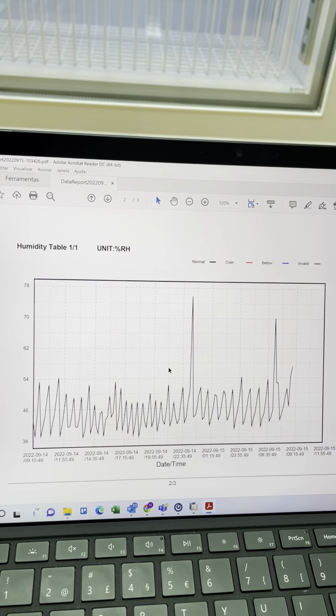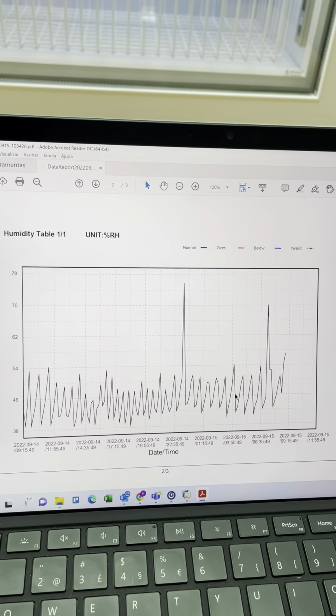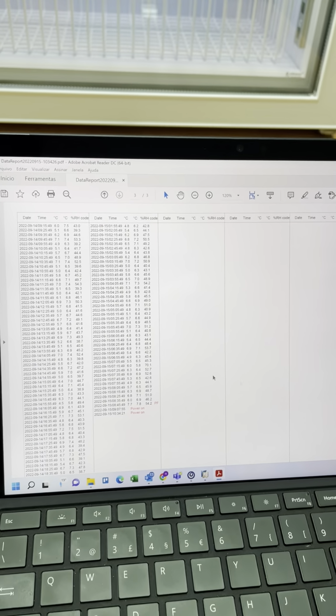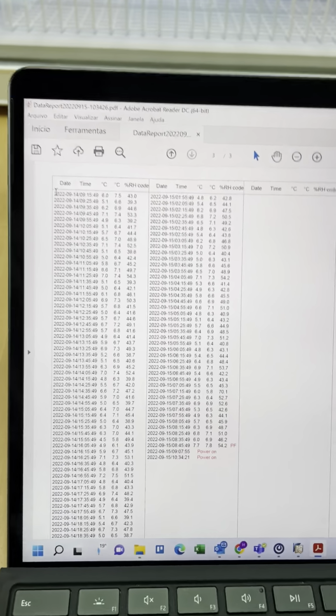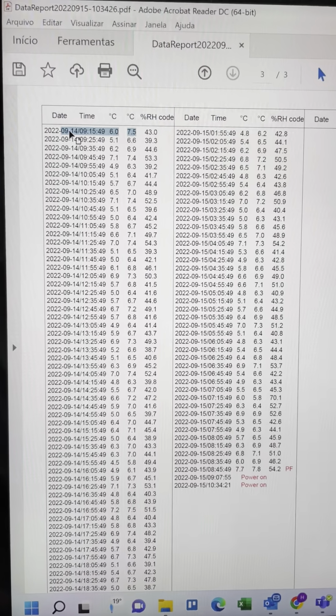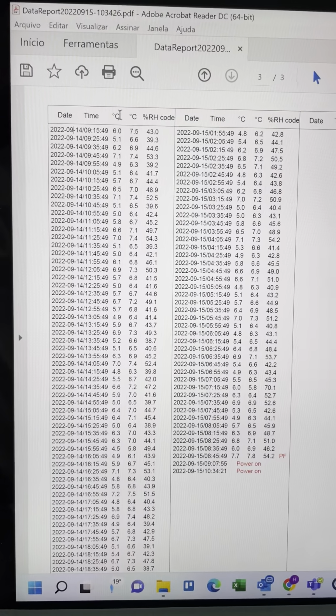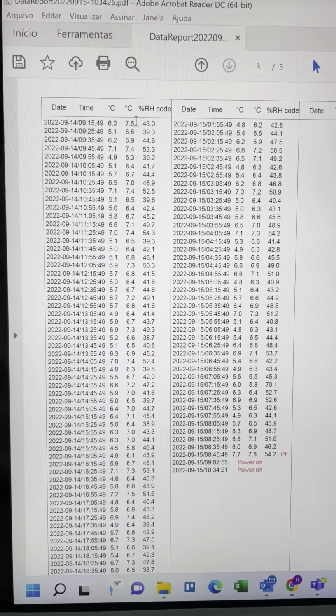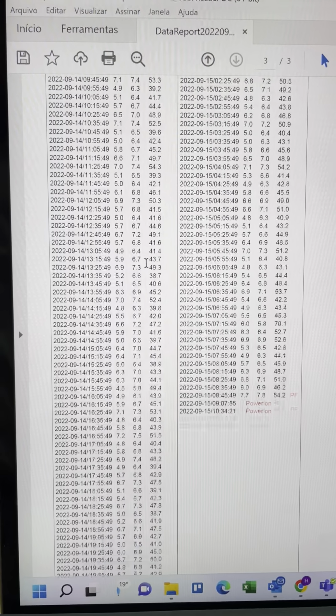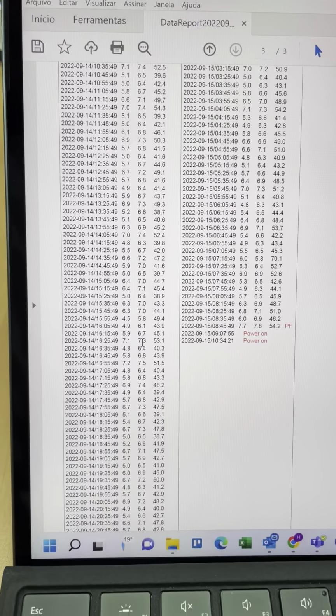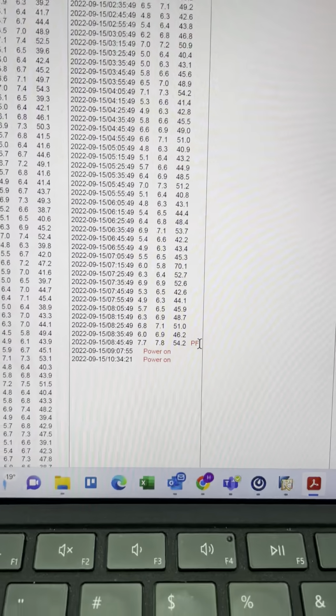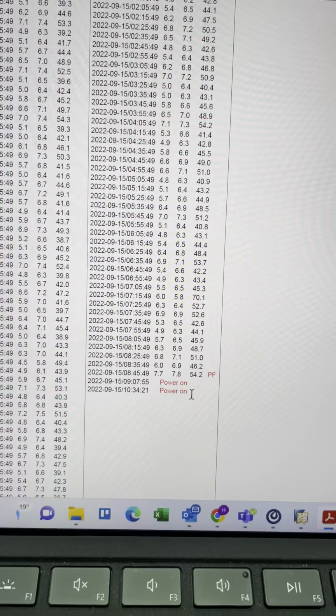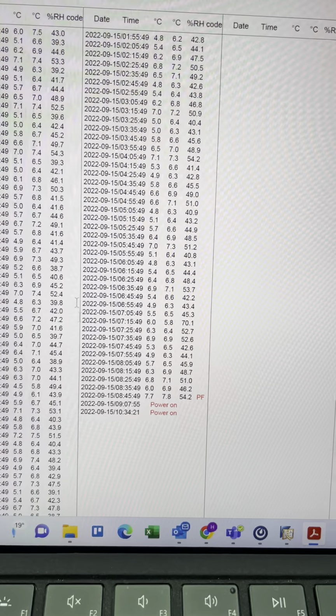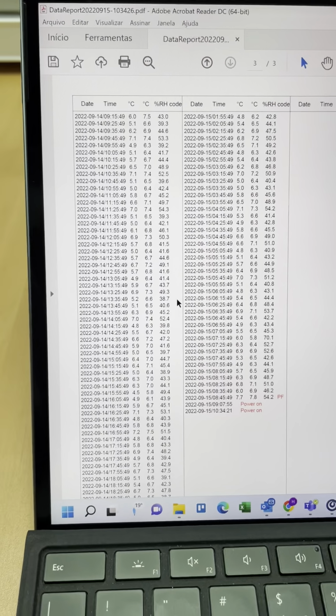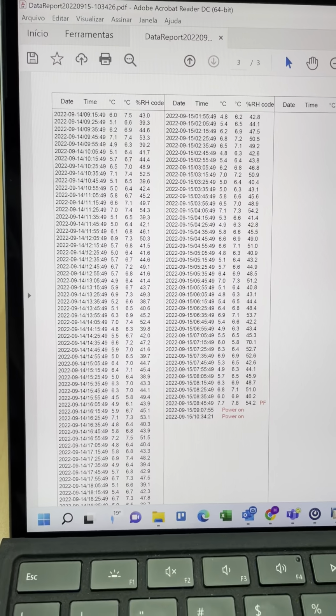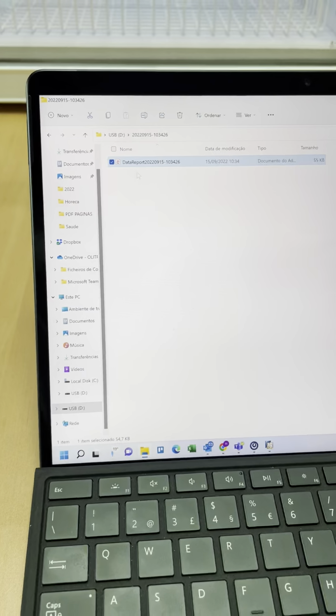In this case, we also had the humidity connected. So here you can see how the humidity was in the equipment. And then you have the data report. You have here the day and time. So this was September 14, 9:15 in the morning. Probe 1 was at 6 degrees, probe 2 was at 7.5 degrees, and in this case you have the humidity. It goes on with all the information here, and when there is an alarm you also have it here. In this case you can see PF, so there was a power failure here, and then it was connected again. When there is a high temperature alarm, low temperature alarm, all of that you will see in red, and then you can see how many times you had the alarm. In this case it's a clean report, you don't have any problem here.